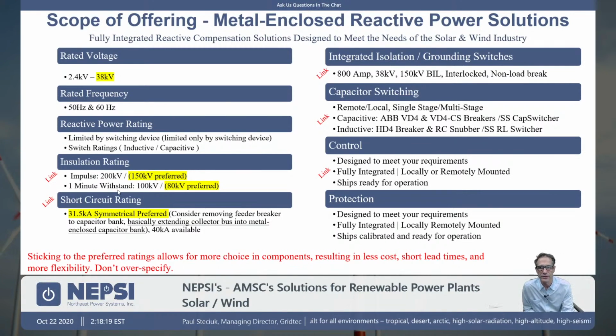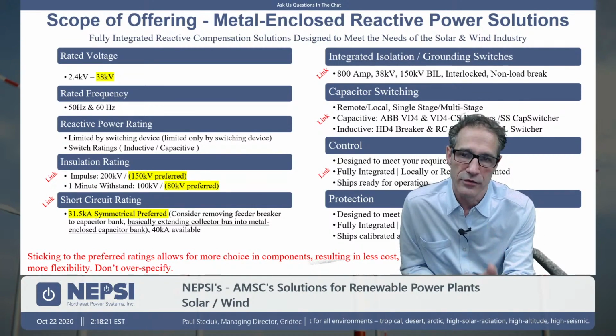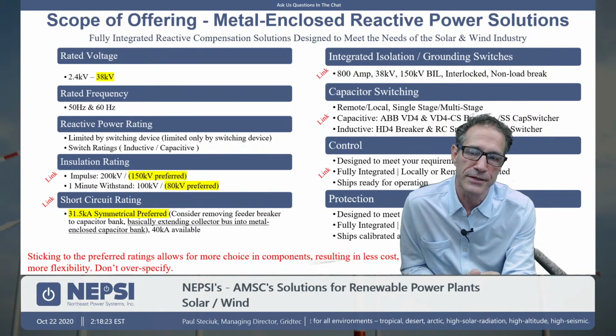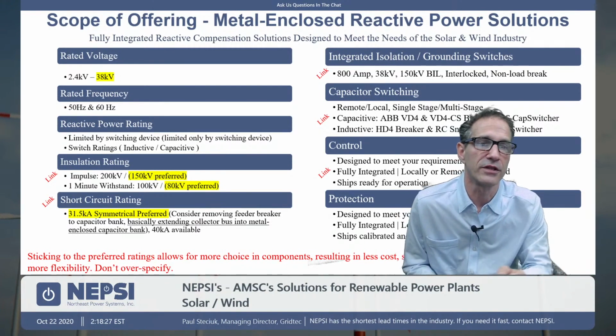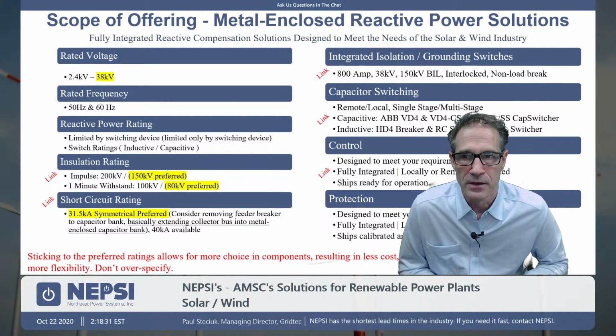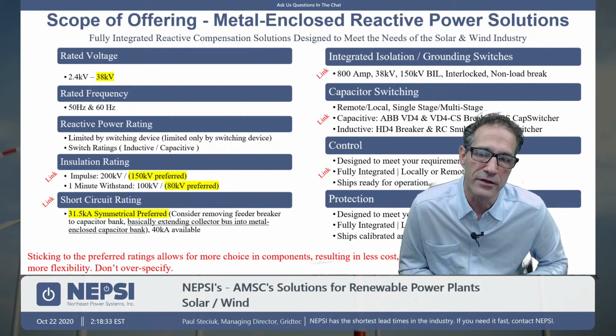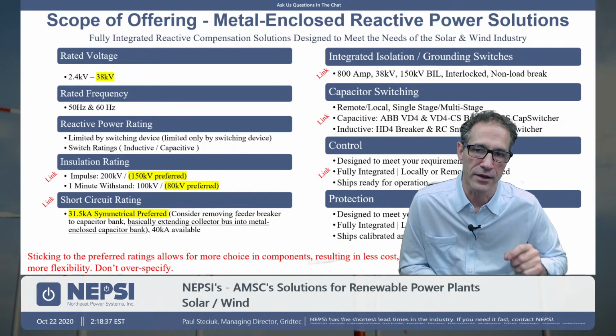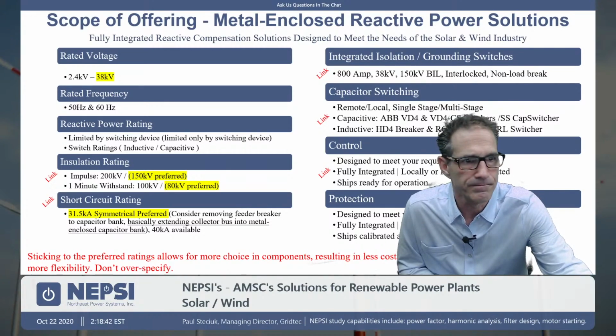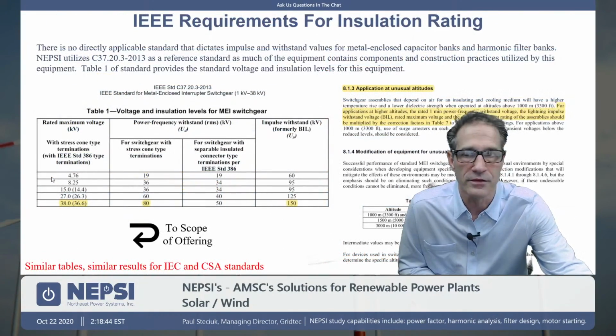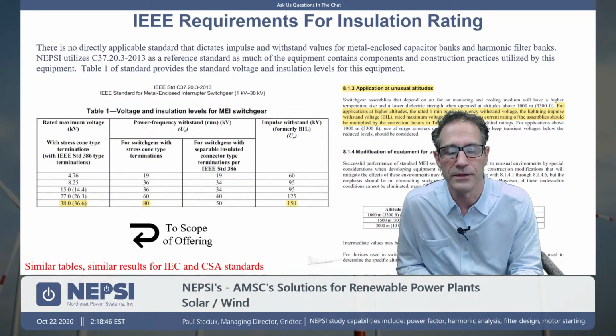When we're talking about insulation rating, we oftentimes see the metal enclosed solution being specified at 200 kV BIL, or we see that the open air system is specified at 200 kV BIL. The point here to be made is that we prefer 150 kV BIL.